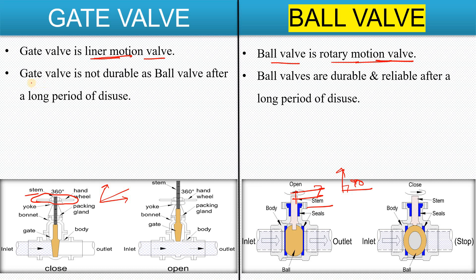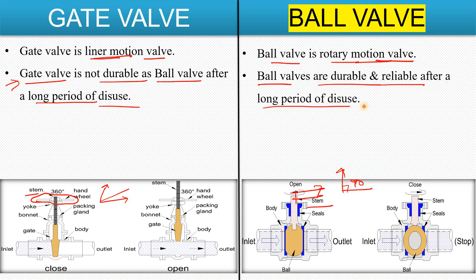With respect to durability, the gate valve is not as durable as the ball valve after a long period of disuse. In lines that only open or close infrequently — such as during shutdown or startup — gate valves are not as suitable. Ball valves are more durable and reliable after long periods of disuse. Leakage problems are more commonly seen with gate valves in such scenarios.